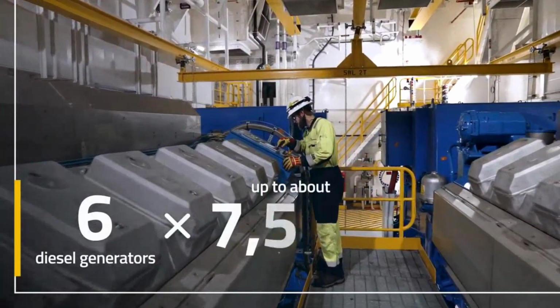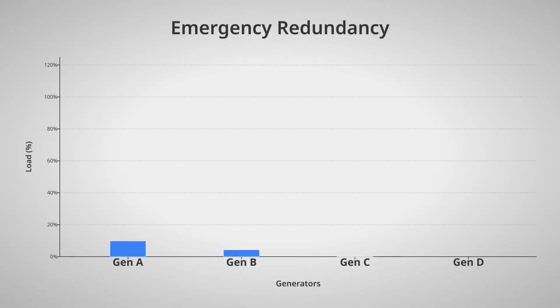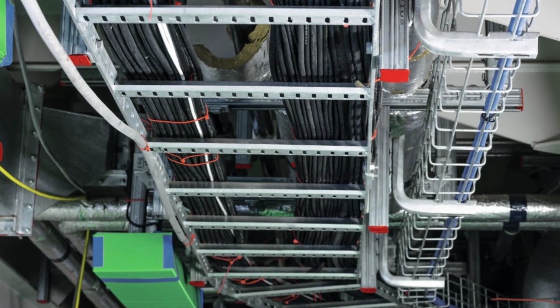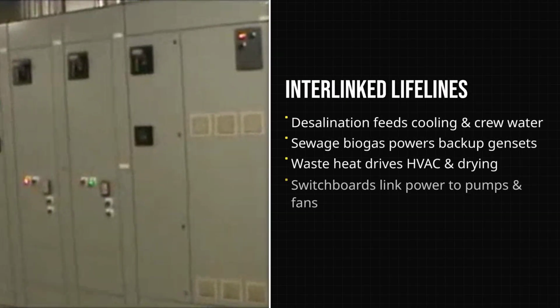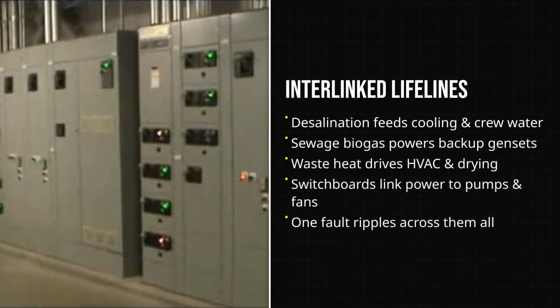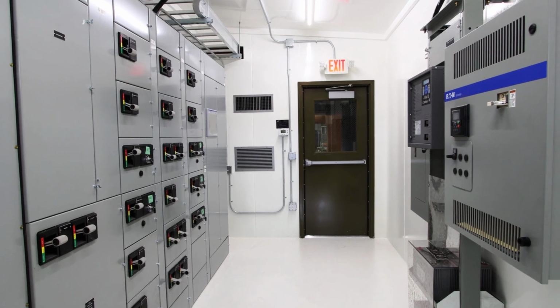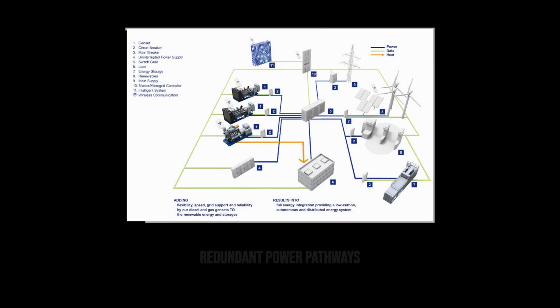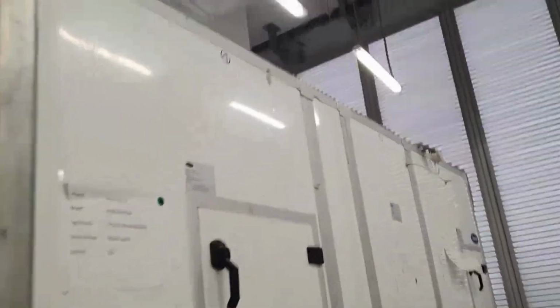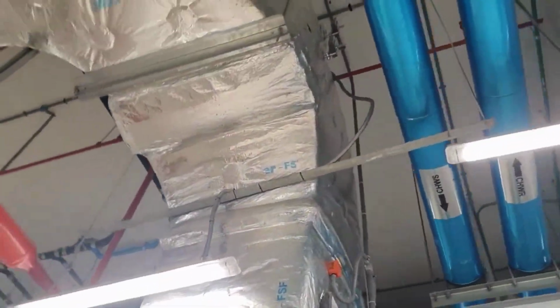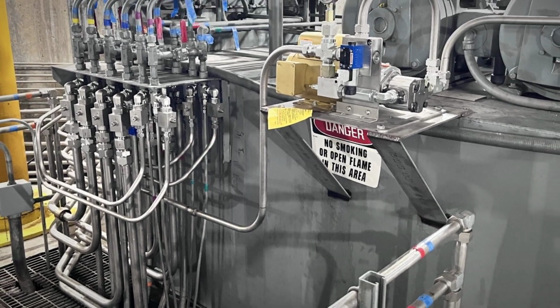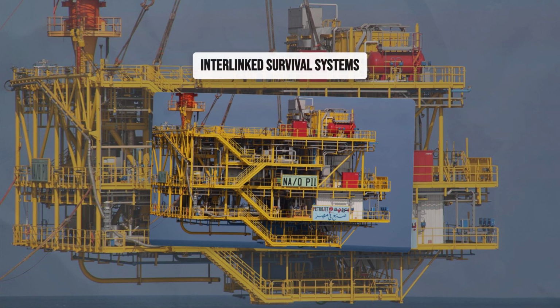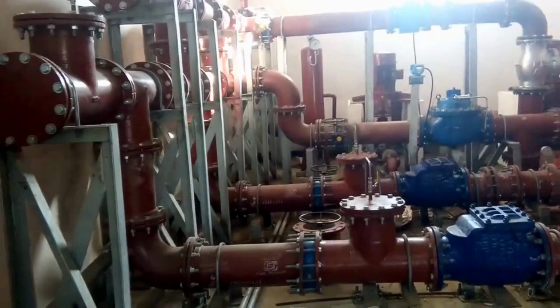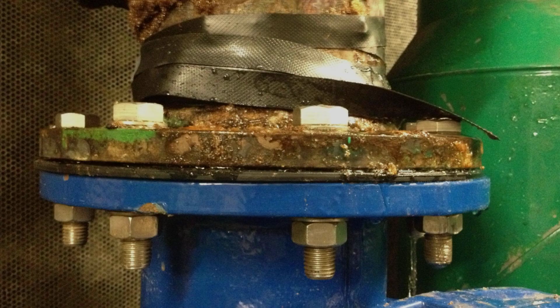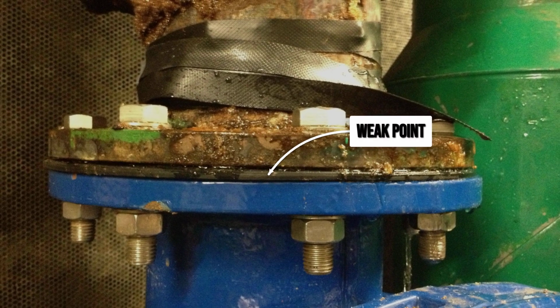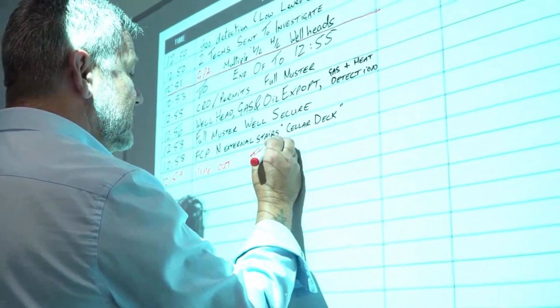Above these utilities, the generator switchboard forms the backbone of the platform's power. Multiple diesel generators run in parallel, each capable of carrying the critical load if one fails. Power flows to every system: lights, HVAC, water makers, and control panels. Switchgear and automatic transfer panels stand ready to isolate faults and keep at least one path open even during a blackout. Air is managed by a central HVAC system, filtering and circulating to maintain pressure and remove dangerous gases. Each component is physically separated and cross-tied, so a single failure does not bring everything down. But every connection is a potential point of weakness, and every shortcut in one system can ripple across the rest.